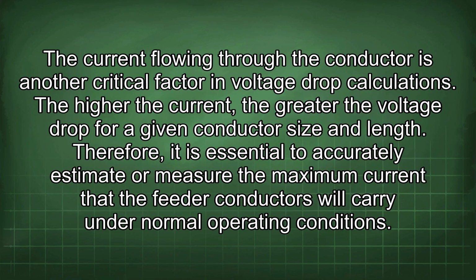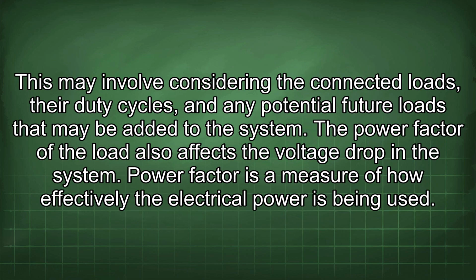The current flowing through the conductor is another critical factor in voltage drop calculations. The higher the current, the greater the voltage drop for a given conductor size and length. Therefore, it is essential to accurately estimate or measure the maximum current that the feeder conductors will carry under normal operating conditions. This may involve considering the connected loads, their duty cycles, and any potential future loads that may be added to the system. The power factor of the load also affects the voltage drop in the system.